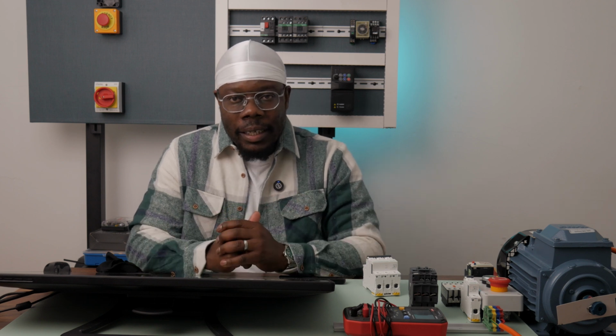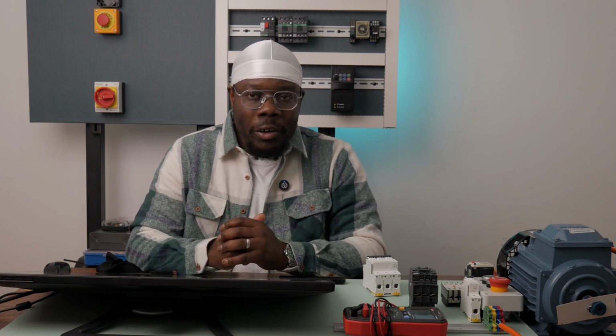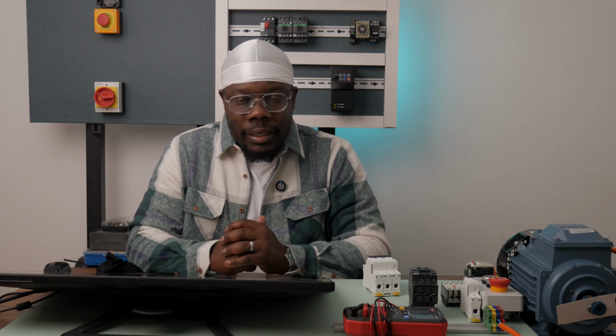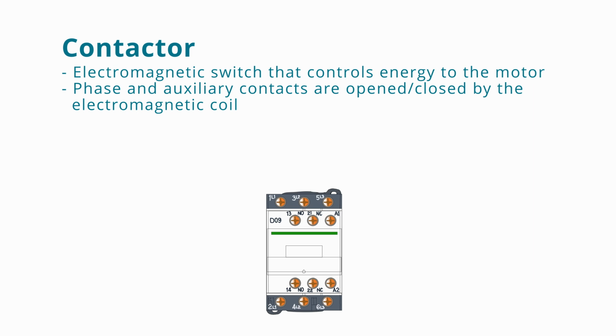Now let's discuss switching in the power circuit. In an electric motor power circuit, we need methods of switching that do not expose the operator to the high switching currents which are associated with switching electric motors. So the contactor, which is activated in the control circuit, allows us to safely switch the supply to the electric motor windings. Now, a contactor is an electromagnetic switch that controls the flow of energy to the electric motor windings. When its electromagnetic coil is energized through the control circuit, it pulls the phase contacts, allowing electricity to flow to the motor windings. This mechanism allows for the switching of high-power devices using low-power circuits. Auxiliary contacts, which are part of the control circuit, also rely on the operation of a contactor.